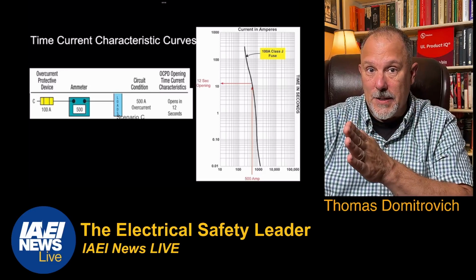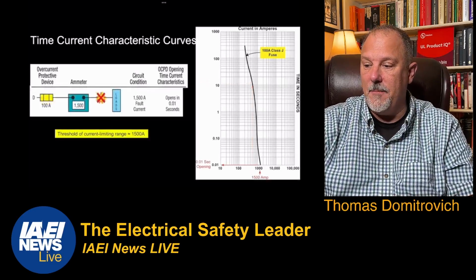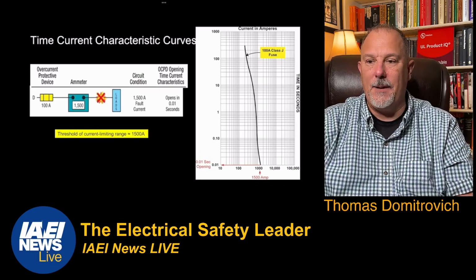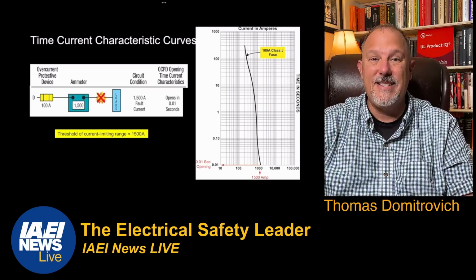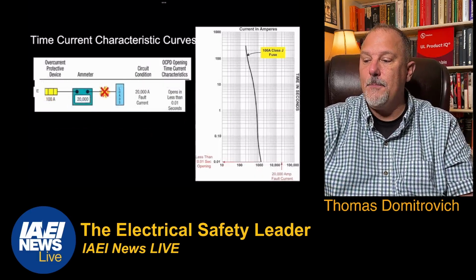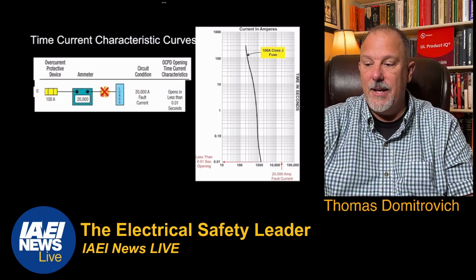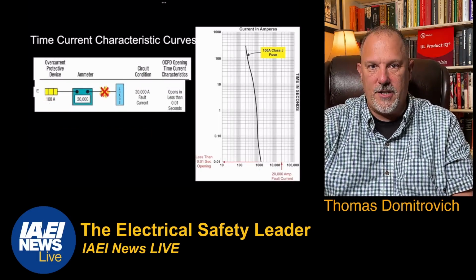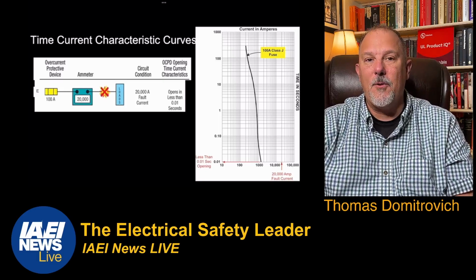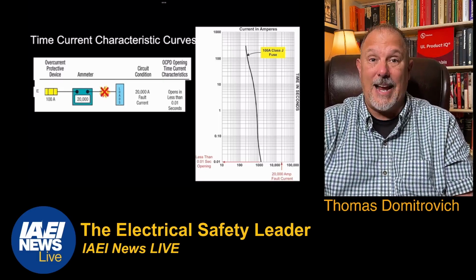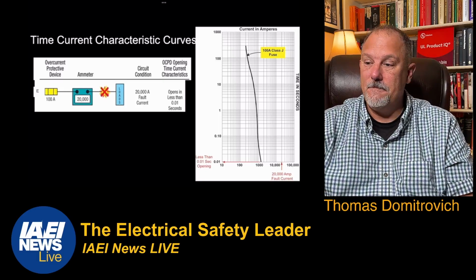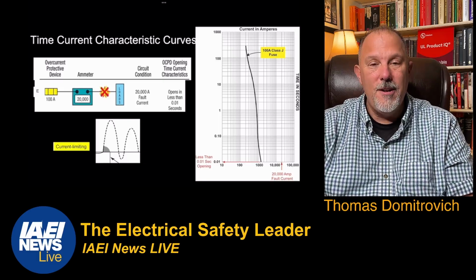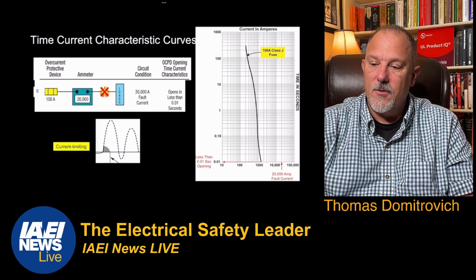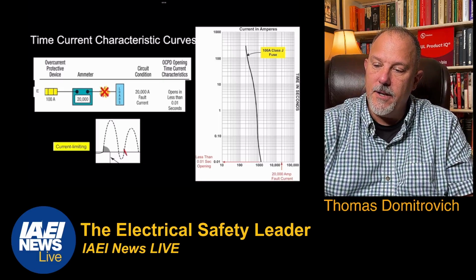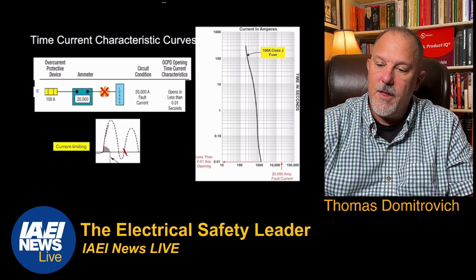So higher currents, faster clearing time. I put 1500 amps and it's going to clear in 0.01 seconds. If I put 20,000 amps, it's going to clear in less than 0.01 seconds, probably around 0.004 seconds. That's a quarter of a cycle. Remember, this right here is one cycle. That is one cycle.